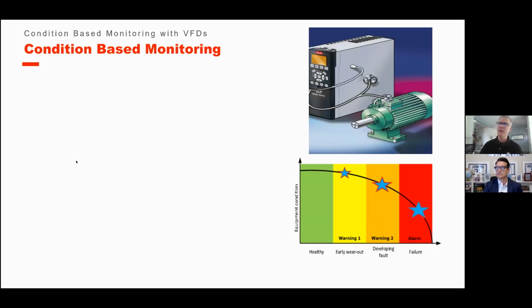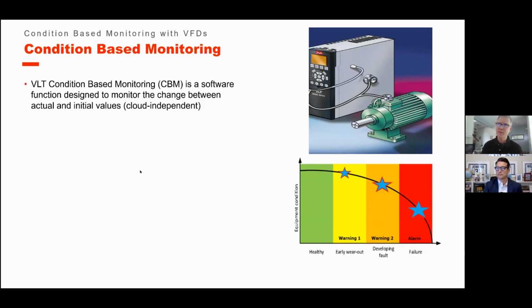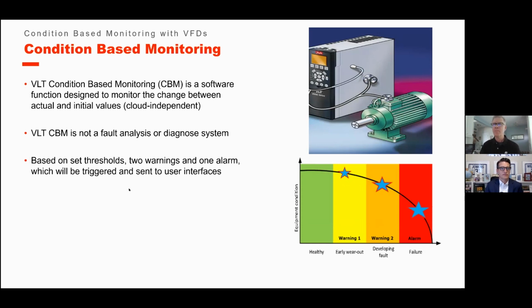The next thing we talk about is condition-based monitoring. Simply put, what is it? Condition-based monitoring is a software function designed to monitor the change between actual and initial values. The CBM is not a fault analysis or diagnose system, and I'll talk about that in a second. It's based on thresholds and warnings.